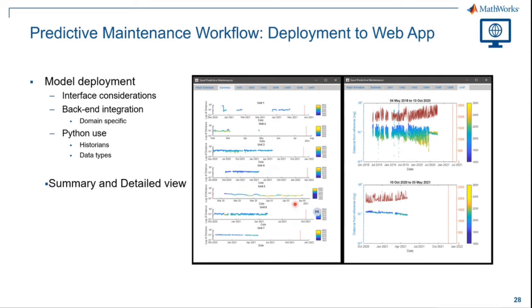high-level look at each machine, and then you can deep dive into a specific unit, so in this case unit 7, and look at what that information looked like for the last wash or the last number of washes in the time frame that you've requested. So here you can actually have that retrospective look to see, did we actually improve? Are we moving further away from that high wheel chamber pressure, getting these nice dark blues and things like that? So that retrospective analysis is done visually, and just as a secondary point to the actual washing procedure itself.